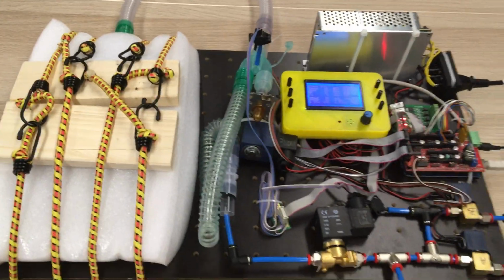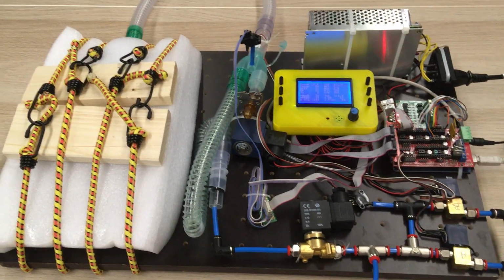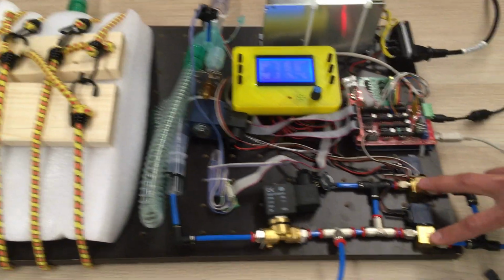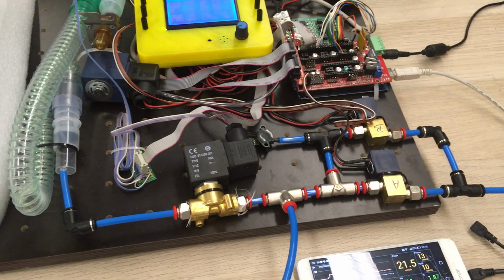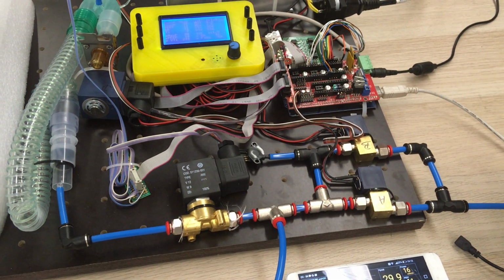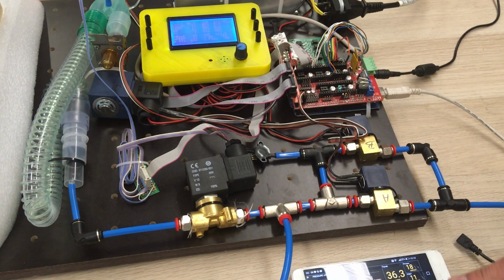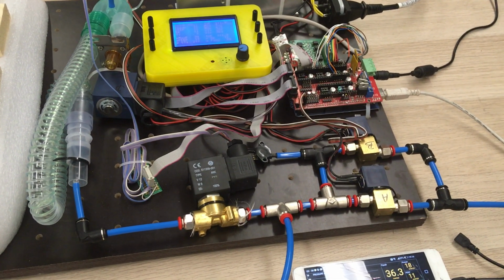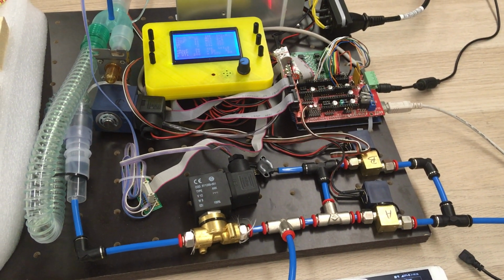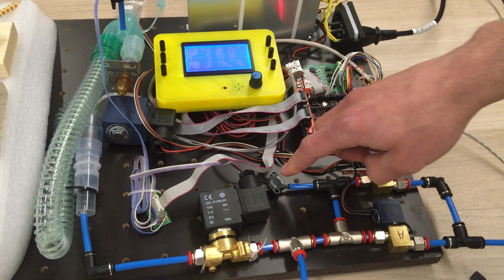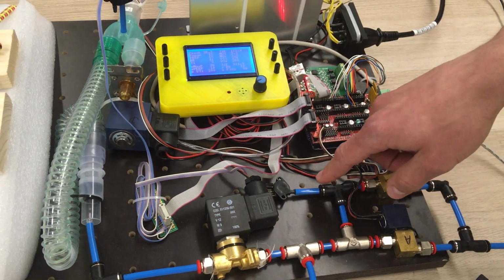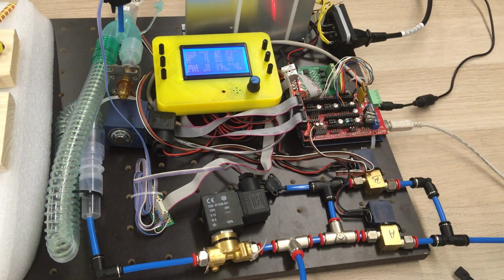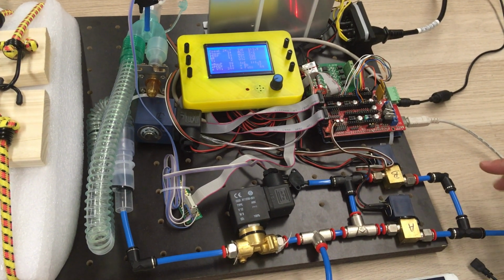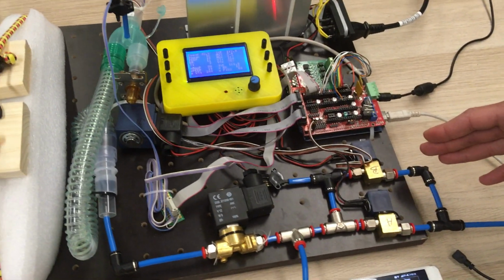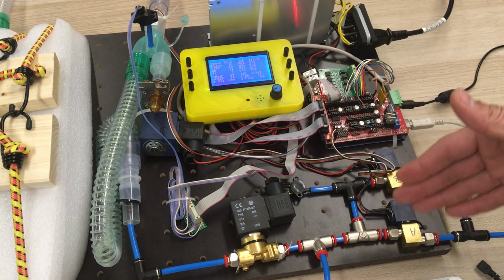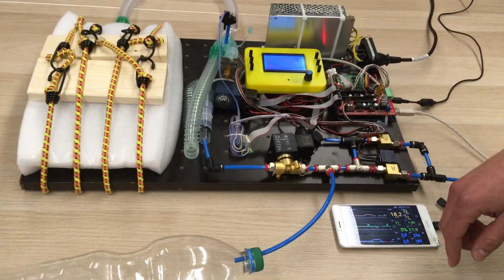Right. Regarding the mixing of FiO2, the principle of mixing is by time division of the first two solenoids. So the time required to fill the bottle is divided into two parts. First the oxygen comes into the bottle, and the increasing pressure during filling of the bottle with oxygen is monitored until a certain division of pressure is reached. Then the oxygen valve is shut, and the air valve is opened, and again we are filling the bottle until we reach the final target pressure.